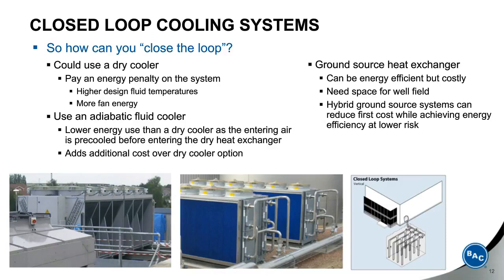Now, you can use an adiabatic fluid cooler, which has lower energy use than a dry cooler, as the entering air is pre-cooled before entering the dry heat exchanger. And you can see a photo of one there in the middle with the blue cooling pads. Water is dribbled over these pads, air goes over the wetted pad, and is cooled adiabatically close to the wet bulb of the air. Now that enhances the dry performance of the coil behind it. Now this does add cost over the dry cooler option.